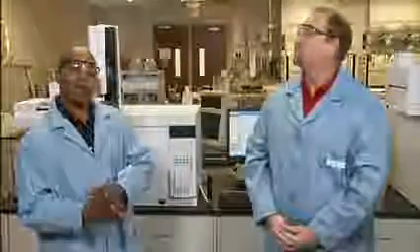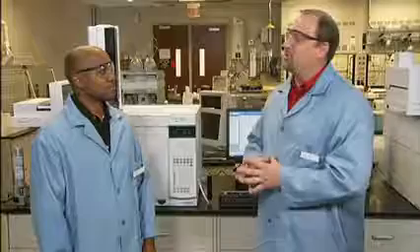Let's summarize key pointers for solving baseline noise. Start with basic GC inlet maintenance. Clean inlet, replace the liner, septa, and gold seal. Bake out your column. Check, and if needed, change your detector gas flow rates. Clean the detector, then replace the old consumables associated with the detectors. And the noise could always simply be contaminated gas. Sometimes this happens when the supplier mis-fills tanks or has a problem. The simple solution is just replace the gas tank. We're making good progress. What other troubleshooting issues do we see most often?